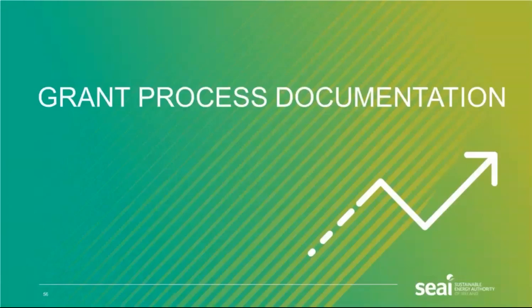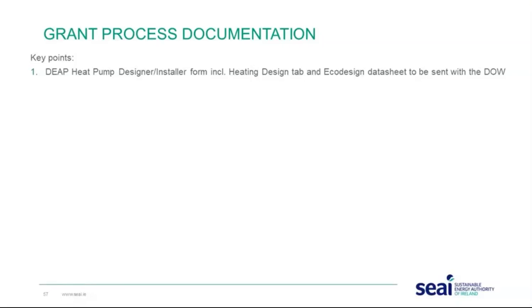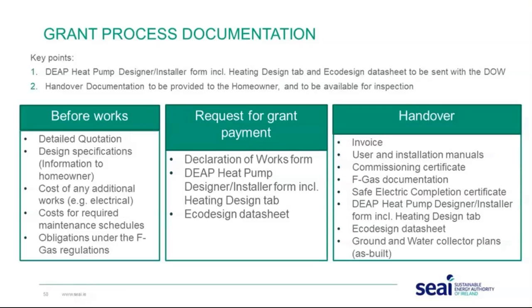That brings us to the grant process documentation. And we have some key points here in relation to this, with the DEAP Heat Pump Designer/Installer form, including the Heating Design tab and ECODESIGN datasheet, which has to be sent in with the declaration of works. And these are the handover documents to be provided to the homeowner, and these should be available for inspection. Now, these are the type of documents we're looking for. Now, there's quite a lot of documents here, but they all have their own importance. Some would be for best practice for business and customer service. Some would be required to comply with the regulations, for example, the F-gas, the Safe Electric, or the RECI cert.